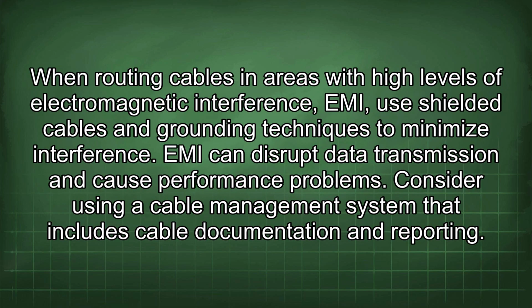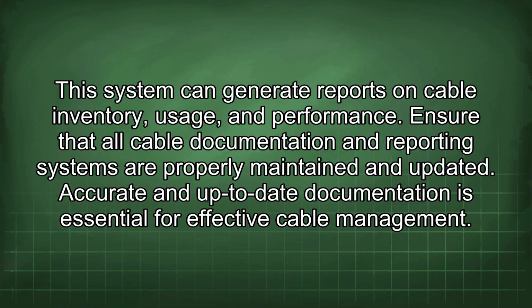When routing cables in areas with high levels of electromagnetic interference (EMI), use shielded cables and grounding techniques to minimize interference. EMI can disrupt data transmission and cause performance problems. Consider using a cable management system that includes cable documentation and reporting. This system can generate reports on cable inventory, usage, and performance. Ensure that all cable documentation and reporting systems are properly maintained and updated. Accurate and up-to-date documentation is essential for effective cable management.